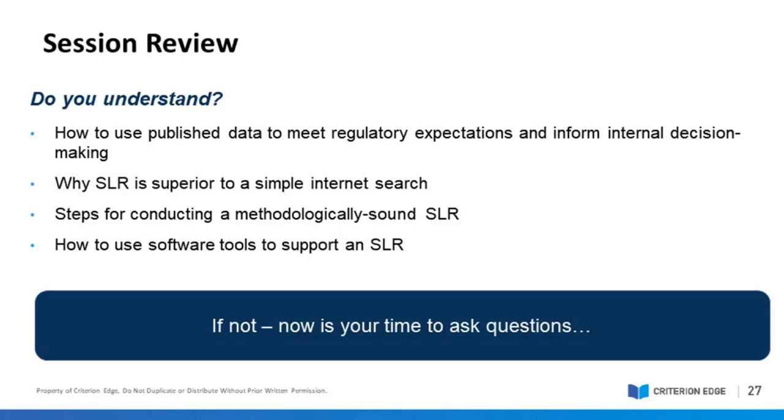So in other words, we work with clients saying we just don't have the time or the manpower or the process yet in place to handle what happens if, during the systematic literature search for the CER, something affects the risk process. That's a risk to the organization. The notified body could clue into that. So the best process is to not proceed with finalizing the CER if there is an update that's needed to the risk management file. Wait until that's done.